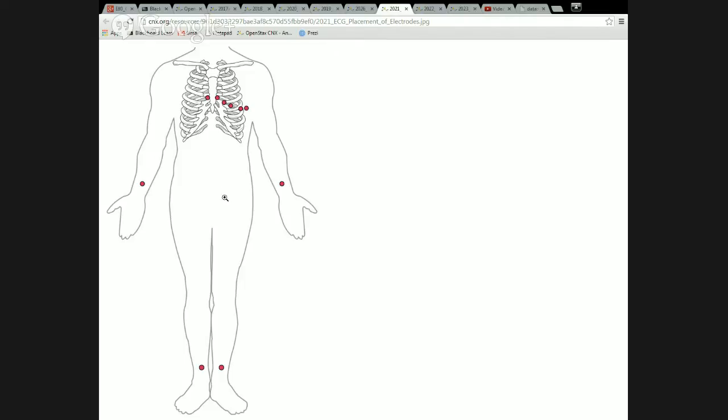These electrodes make it possible to measure the electrical activity that's generated by the heart because somebody discovered a very reliable way to do this. An important part of that is that the right ankle electrode is a grounding electrode. So that basically tells the machine what background electrical activity is going on, and we can subtract that out versus what's recorded at the other electrodes, and we can isolate the electrical activity for the heart specifically.